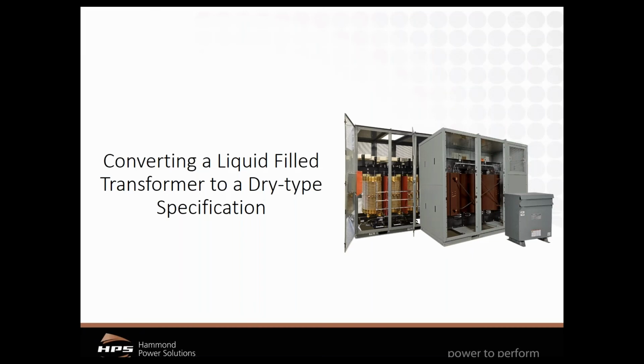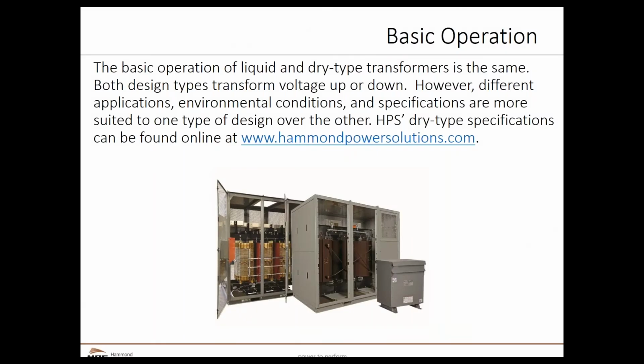When we talk about converting a liquid-filled transformer to a dry type specification, what has to be done in order for us to accomplish that? And again, what we're trying to say is that the basic operation of liquid and dry type transformers is the same. A lot of times we're changing voltage, we're possibly providing some harmonic mitigation depending on how the phases are arranged. We might obviously be providing short circuit mitigation, stuff like that.